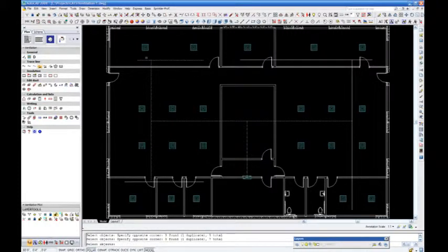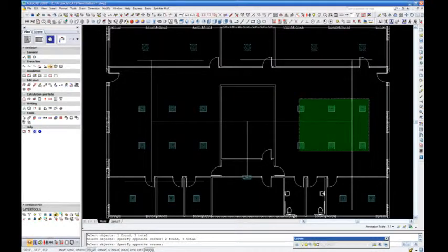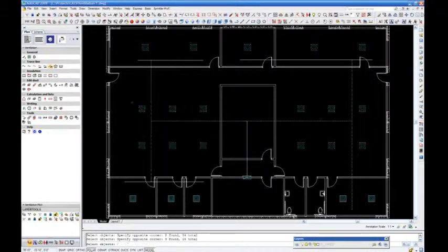Once our center line is completed, under the CATS Commander, under Ventilation, select Trace Line, Repair Trace Line Global. After selecting the center line, we are creating a trace line. Now we are connecting our diffusers automatically to our trace line. In the AutoCAD command, we are asked to select the diffuser. In this case, we select all diffusers. Next, we are asked to select the trace line to which the diffusers will be connected.